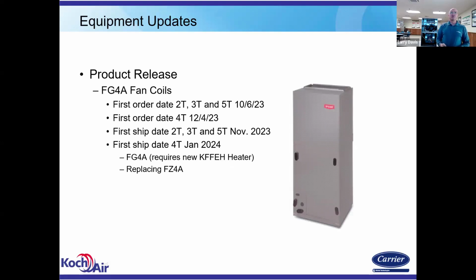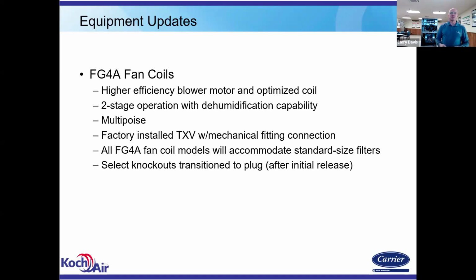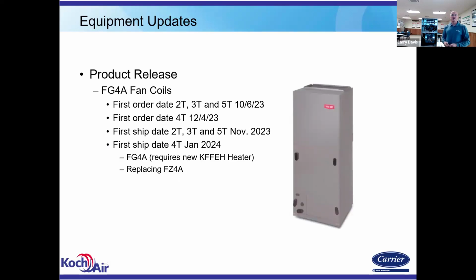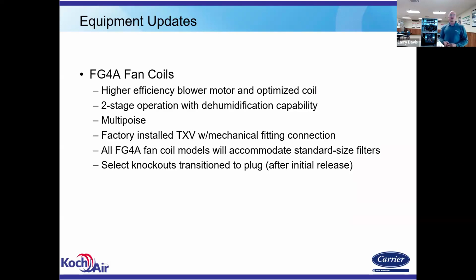Okay, new mid FG4 air handler. Again, this is just a new product. These are older slides. These things are already out. Same thing, it's going to have the knockout transition. One thing to note is that this replaces the FZ4, the FG4. You have to make sure you get the right heat kit for the right air handler. If you're doing a change out of an air handler, just because that heat kit might look the same, it probably is going to wire differently for the new air handler. And the majority of the time you'll find out when you go to plug the two plugs together and they're both male plugs. They won't match. So you've got to make sure you get the right heater for the right air handler.